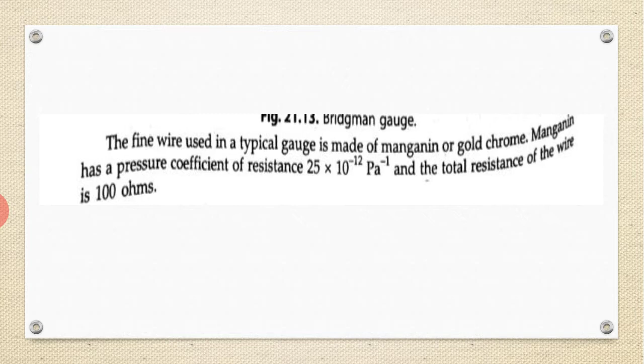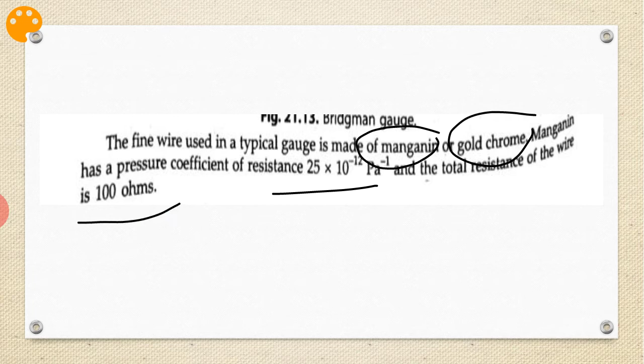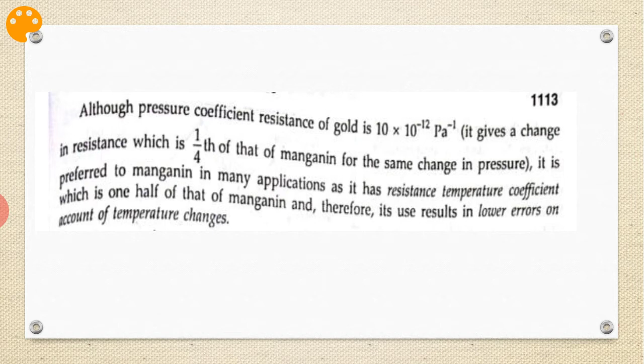Let us see which type of wire they are using. The fine wire used in the gauge is typically made of manganin or gold-chrome. The total resistance of the wire is nearly 100 ohms. The pressure coefficient of resistance of gold is given as 10 into 10 raised to minus 12. It gives a change in resistance which is one-fourth of that of manganin for the same change in pressure, and it also has a lower resistance temperature coefficient than manganin, and therefore results in lower error on account of temperature changes. So this is the information related to the wire used here.